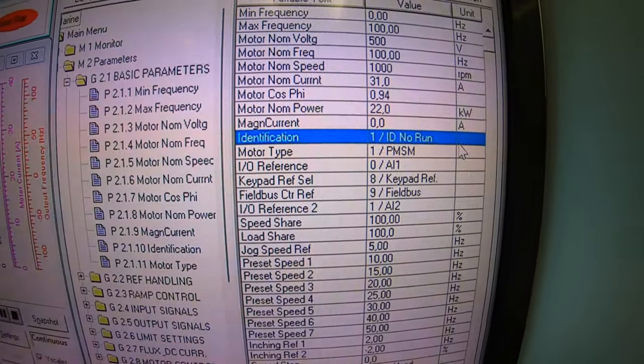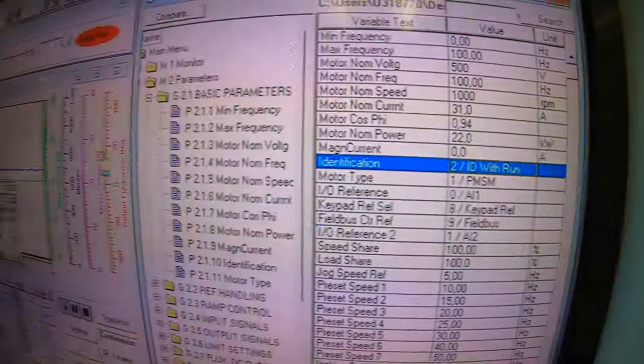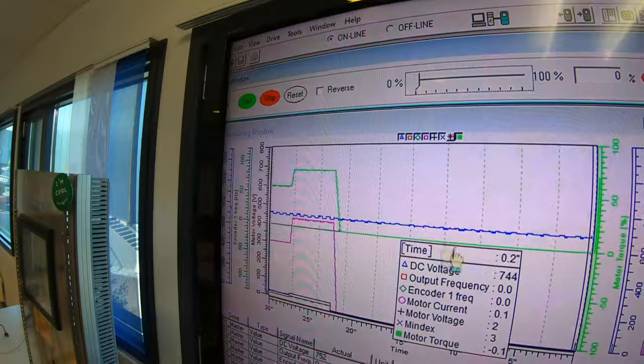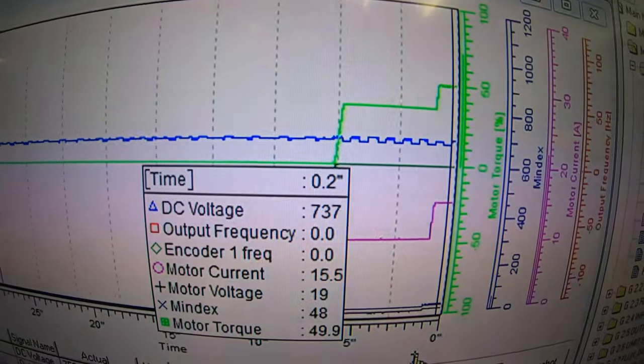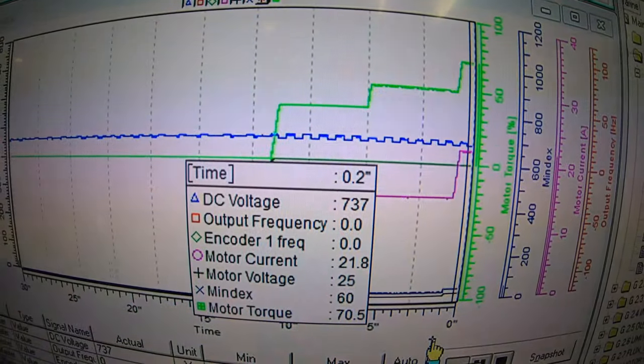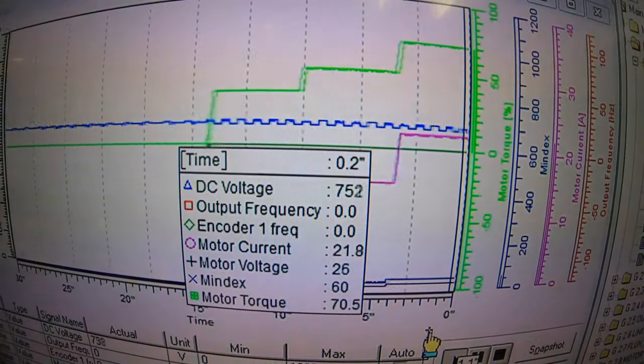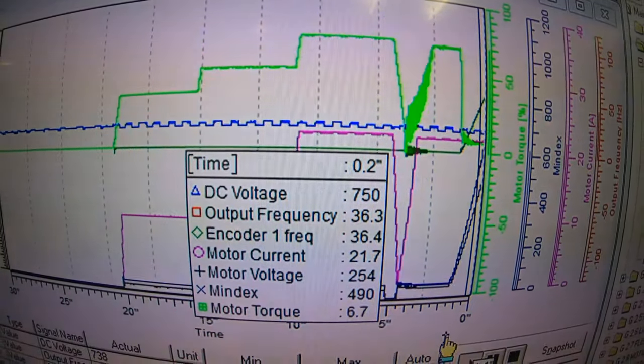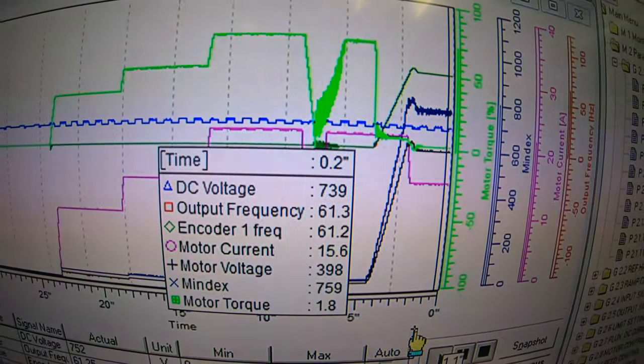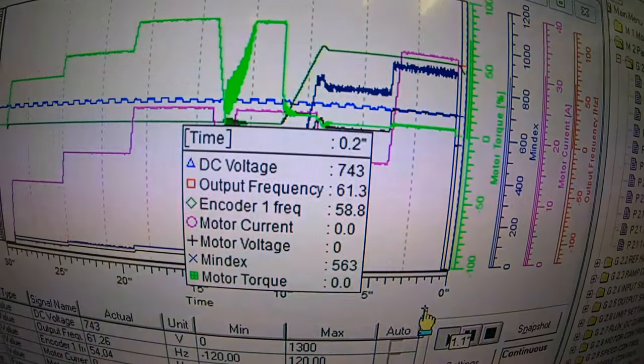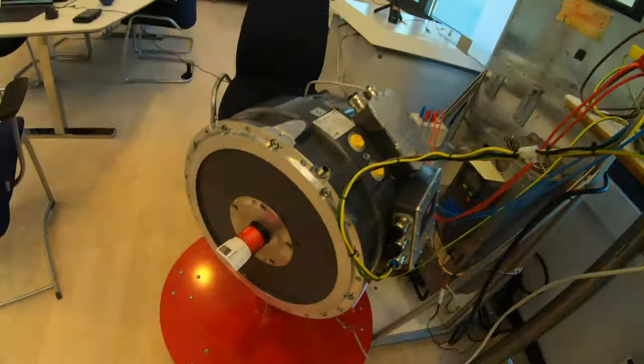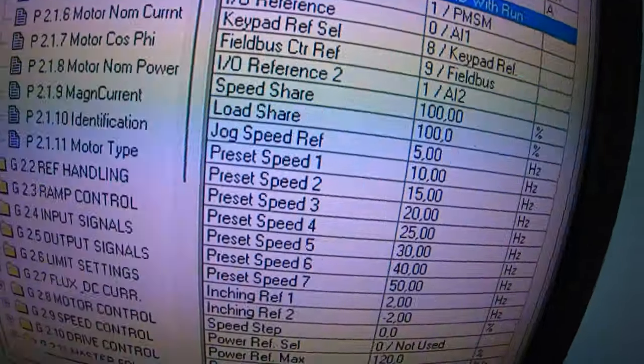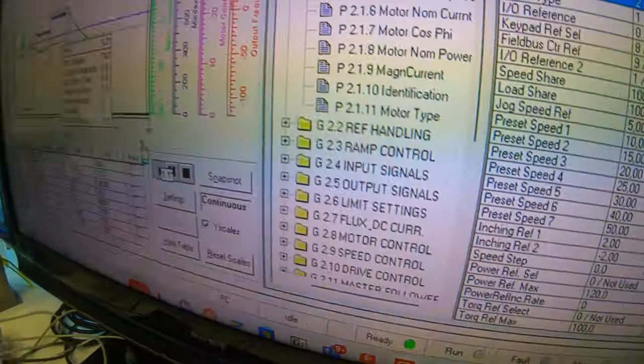I also do one identification run now with rotation. So I select with rotation and same thing, I go to the start button and I sit back, no hands. And it will do identification run without rotation first, and then it will start rotating after this. It is important that the shaft is free, and if there had been a ship propeller on now, there is quite limited how much torque you can tolerate during an ID run. Now it was finished and the rotation has stopped. I can see from my status here that it went well.